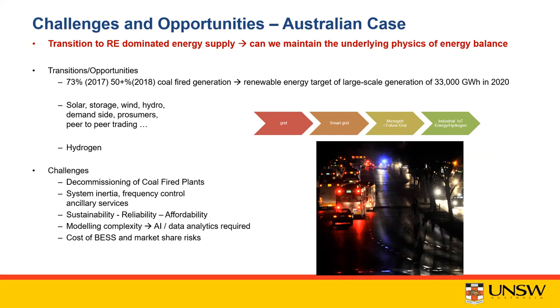As an interim but very effective solution, there were a number of battery energy storage projects, including the famous Tesla battery, or what we call the Hornsdale Power Reserve, located in South Australia, providing much needed system support. In a recent event in South Australia, the Hornsdale Power Reserve did very fast charging and discharging, over 60 megawatts in a very short time. So there was no load curtailment in South Australia, but there were major load cuts in neighboring Victoria and New South Wales. This shows the effectiveness of energy storage in providing much needed energy balance when things happen in the network.